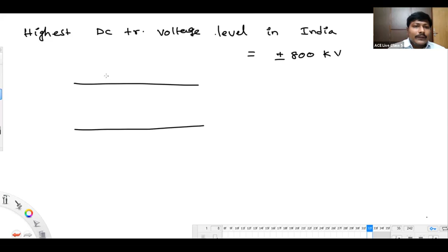Plus or minus 800 kV means we have two wires here. One is a positive polarity conductor at 800 kV, and the next one is a negative polarity conductor at minus 800 kV. We have two wires, two paths you can say. The first wire is operating at plus 800 kV, the second wire at minus 800 kV. That's the meaning of plus or minus 800. You should not say the conductor to conductor gap is 800. And this type of line we call a bipolar line.